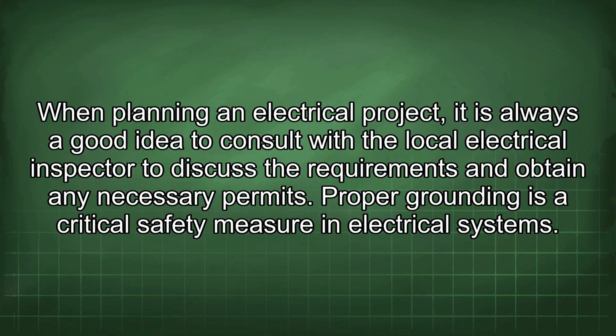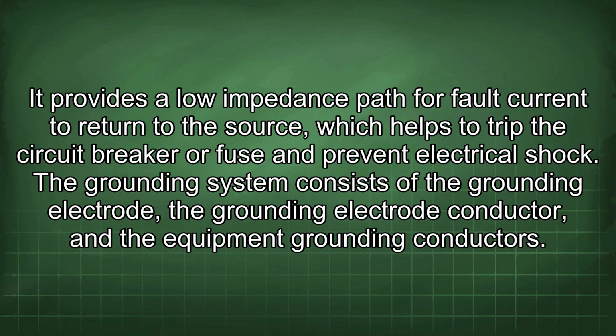Proper grounding is a critical safety measure in electrical systems. It provides a low impedance path for fault current to return to the source, which helps to trip the circuit breaker or fuse and prevent electrical shock. The grounding system consists of the grounding electrode, the grounding electrode conductor, and the equipment grounding conductors.